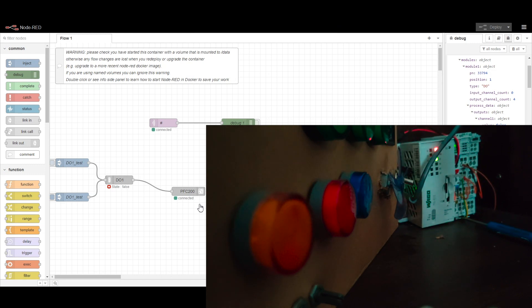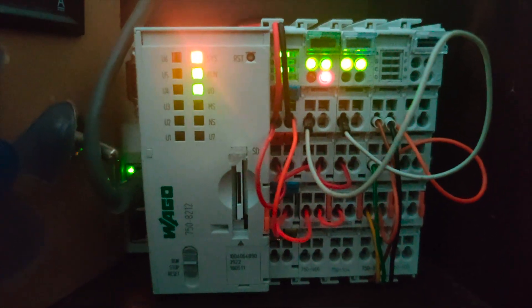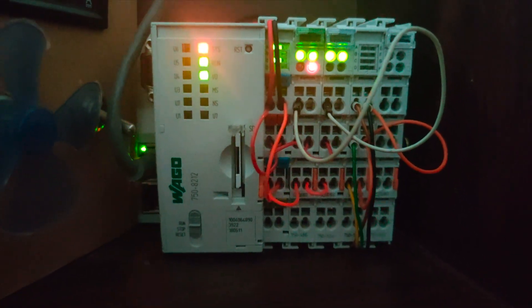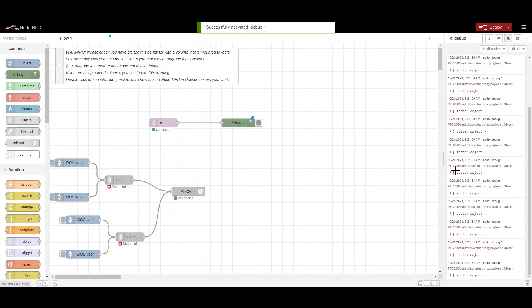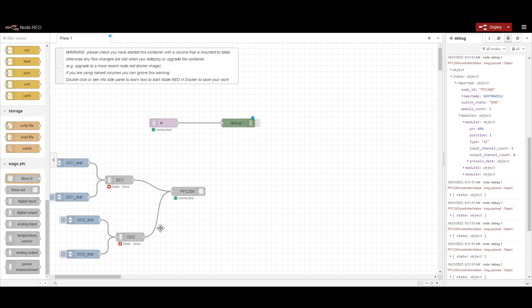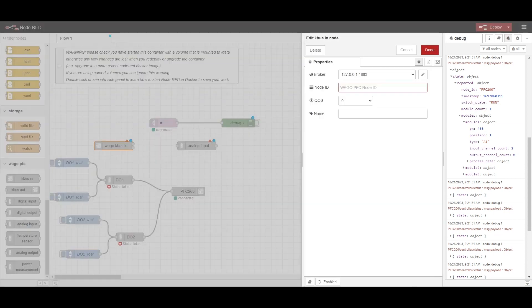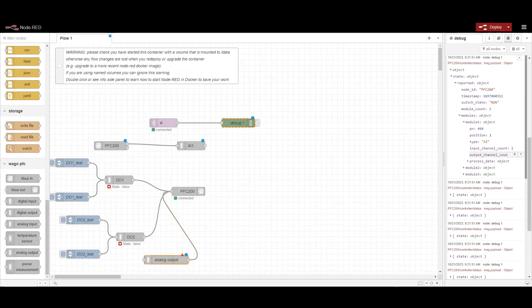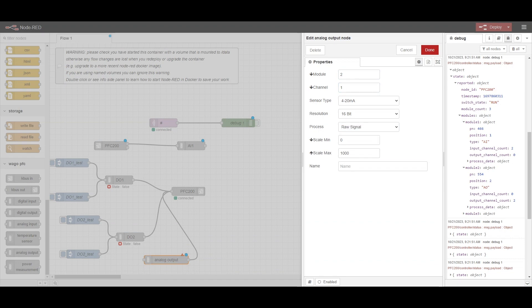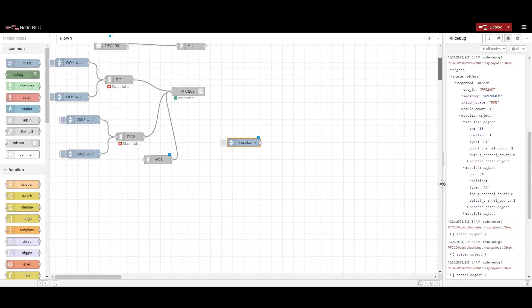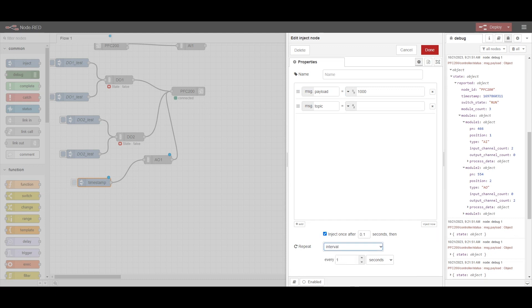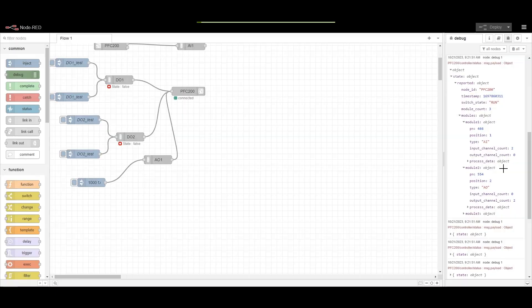Now let me show how to configure analog inputs and analog outputs. I have changed the configuration — now I have three cards: one analog input, one analog output, and one digital. The analog output is looped back to the analog input, so whatever command we give to the analog output will be reflected in the analog input. We perform the same configuration providing the module and channel numbers, and also specify the signal type — 4 to 20 mA or 0 to 10 V.